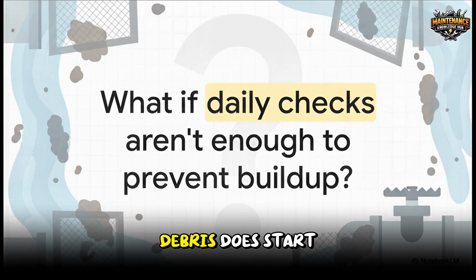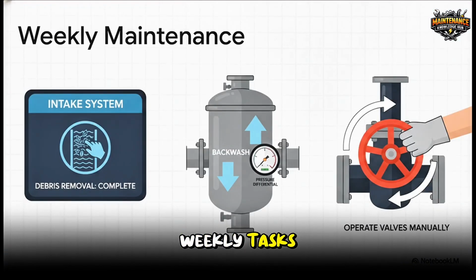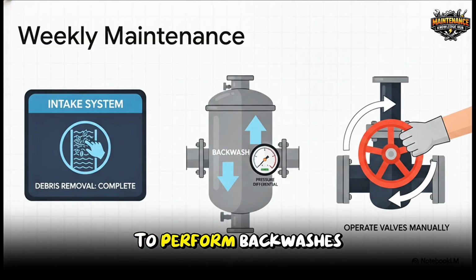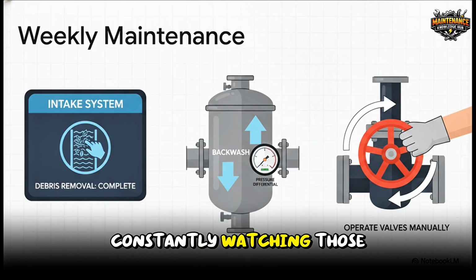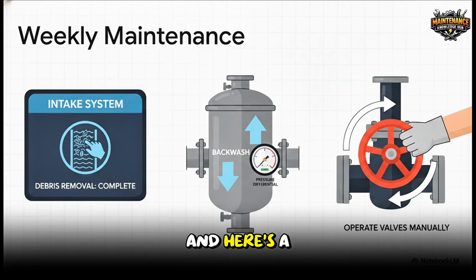Because eventually, debris does start building up in the system. Well, moving to weekly tasks, that's where we tackle the physical reality of moving mass amounts of water. You've got to clear out the debris and sludge from your intake screens. You absolutely need to perform backwashes on your sand and activated carbon filters, constantly watching those pressure differentials. And here's a big one, manually operating your valves every week. It's a use it or lose it situation. Doing this prevents them from getting stuck when you desperately need them during an emergency.